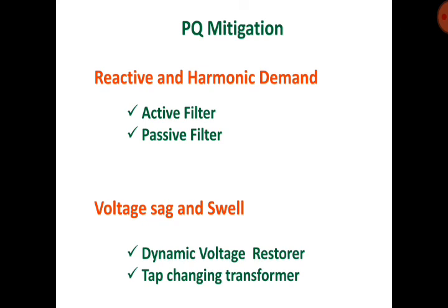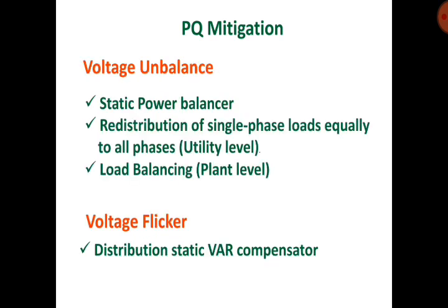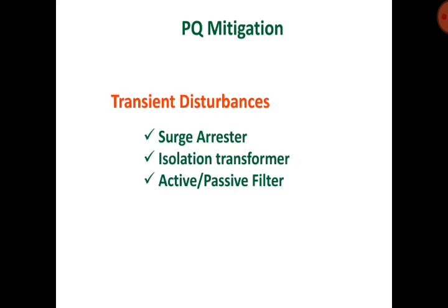Power quality mitigation: reactive and harmonic demand can be mitigated by active filter and passive filter. Voltage sag and swell can be addressed by a dynamic voltage restorer and tap-changing transformer. Voltage unbalance can be mitigated by a static power balancer, redistribution of single-phase loads equally to all phases at utility level, and load balancing at plant level. Voltage flicker can be mitigated by a distribution static VAR compensator. Transient disturbances can be addressed by surge arrestors, isolation transformers, and active or passive filters. This concludes the discussion on power quality issues.